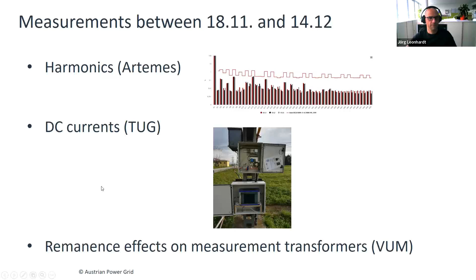We have made several measurements in these 4 weeks. The harmonics were tested by our subcontractor Artemes, and they were all within the limits. We measured also DC currents together with Professor Renner from Technical University of Graz in order to assess the amount of DC currents infed into our system, because that could cause problems in the noise of the transformers or remanence effects on measurement transformers. This was also measured, and we have had some interesting results from these measurements. The system was in the end decommissioned on the 17th of December within 3 days. So that is very fast possible and very smooth.